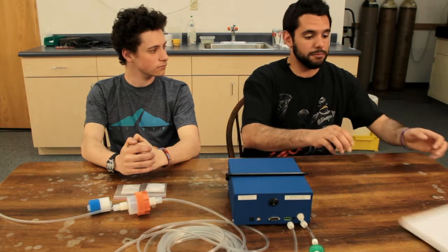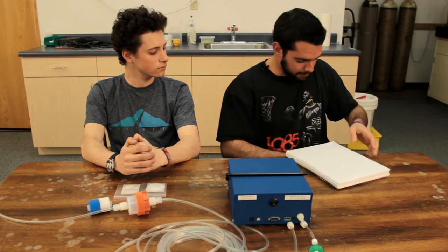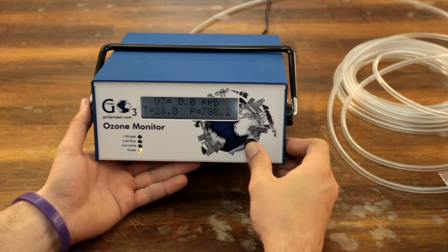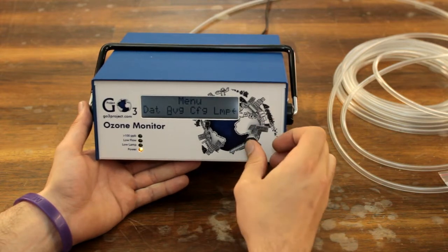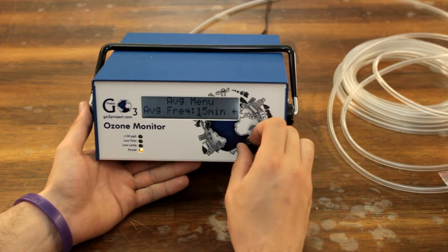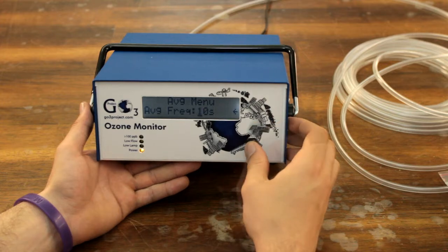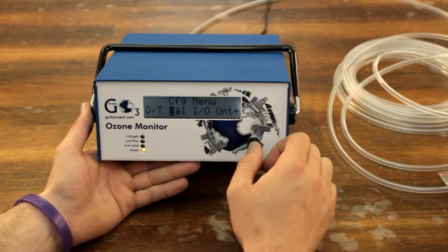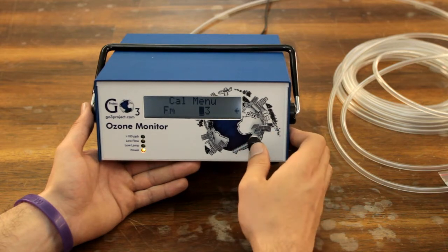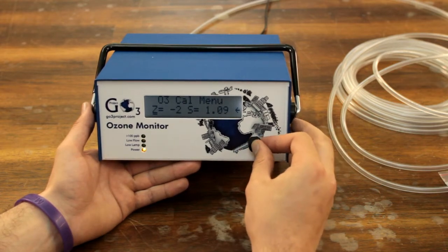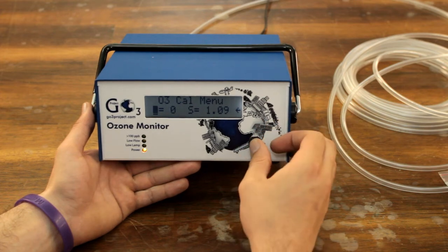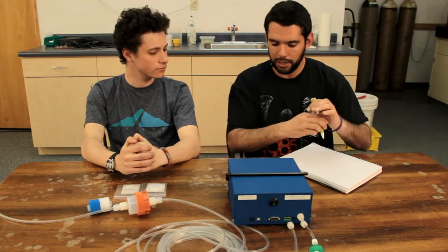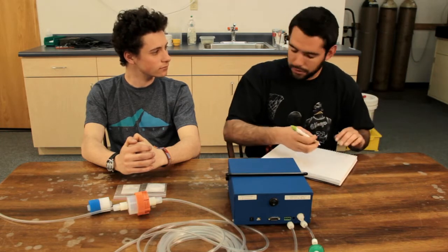The way that we're going to do the measurements is we're going to change our measurement time to 10-second measurements. So we'll go into Menu, Average, and change it to 10 seconds instead of 15 minutes. We'll also go in and change our Z. So we'll go to Menu, CFG, Cal, and we'll change that Z to 0. Once we've done that, we'll go back to the main display screen on the monitor, and we'll take about 20 measurements of what's going on.